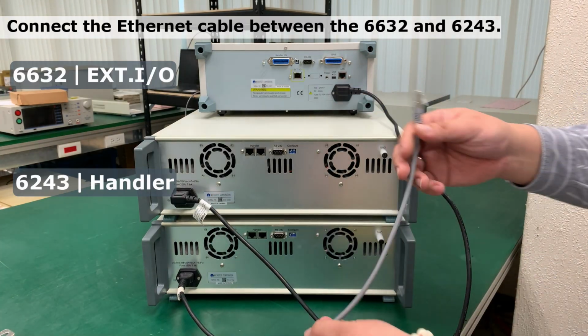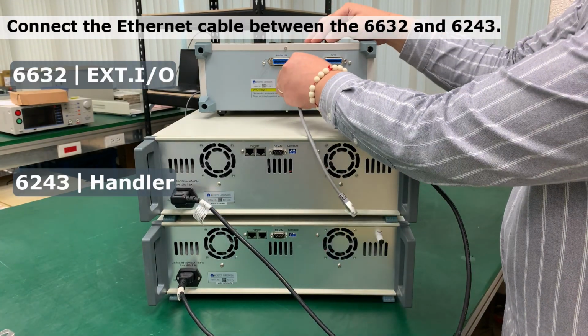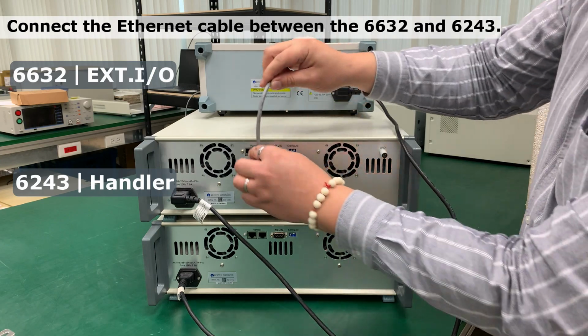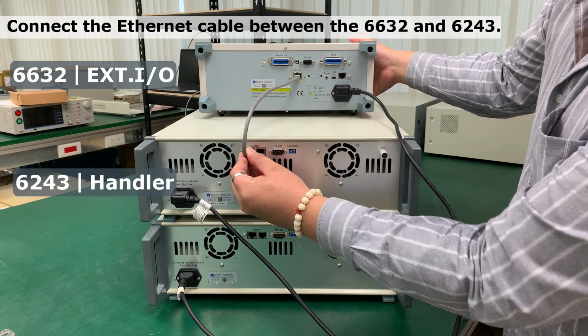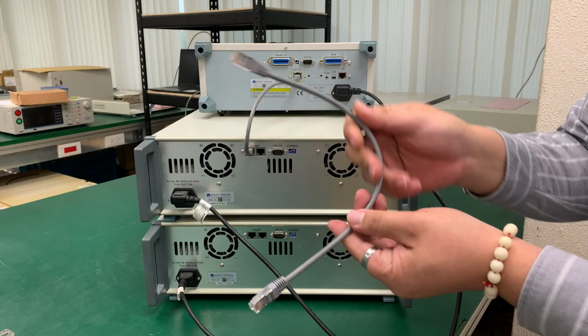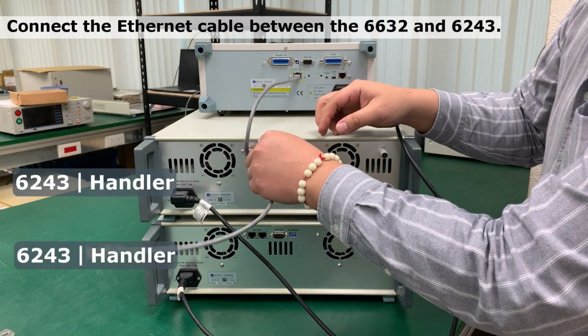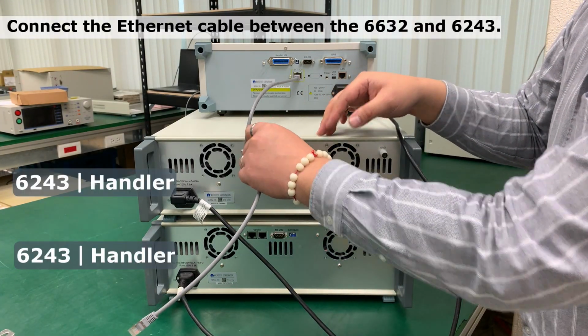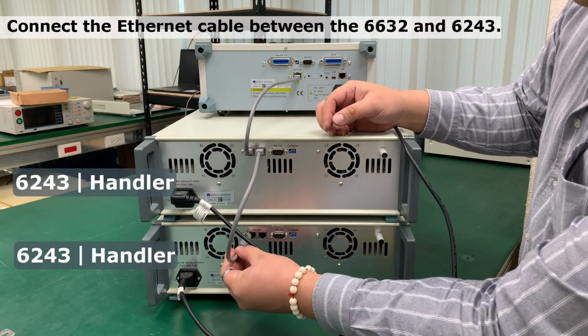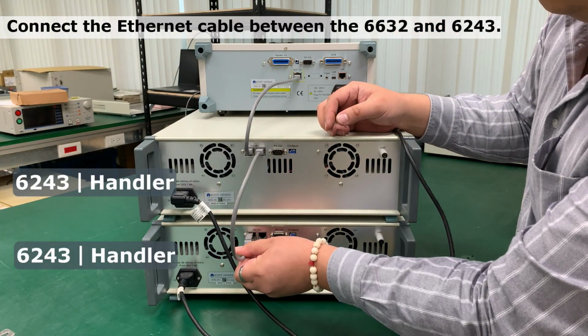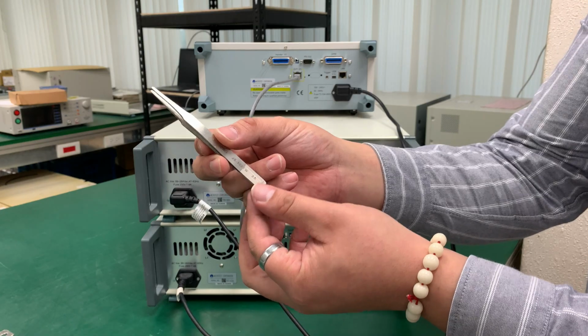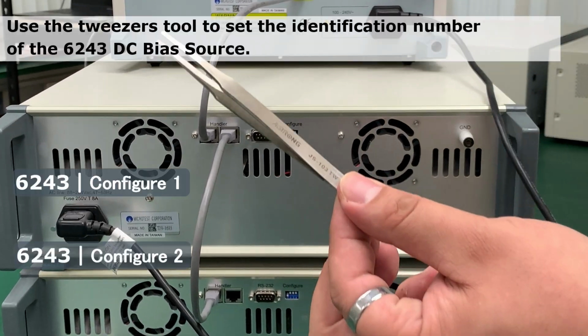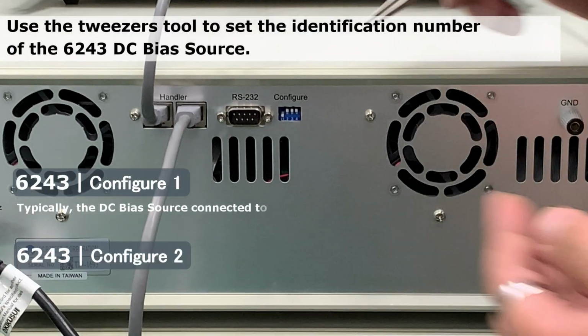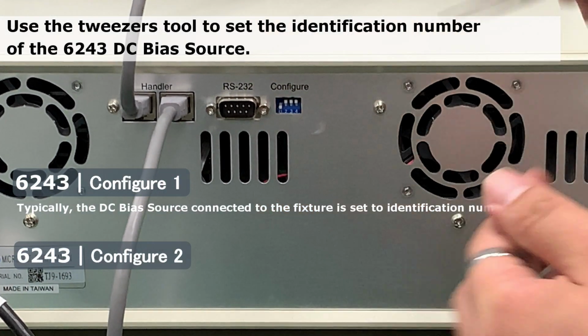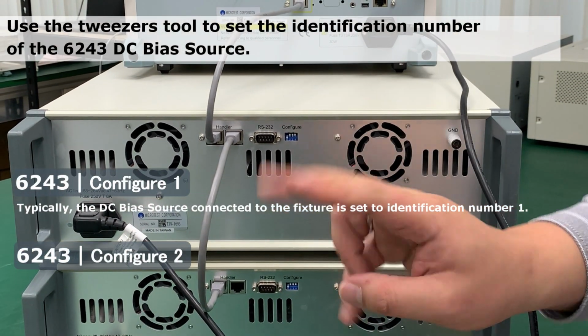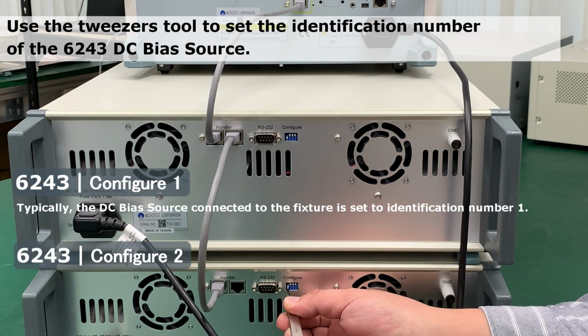Connect the 6632 impedance analyzer and 6243 DC bias source using Ethernet cables. Use the tweezers tool to set the identification number of the 6243 DC bias source. Typically, the DC bias source connected to the fixture is set to identification number 1.